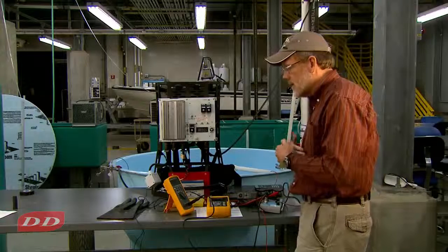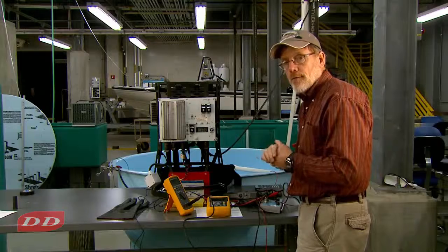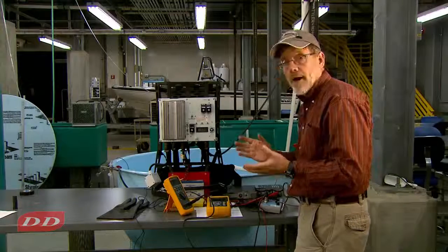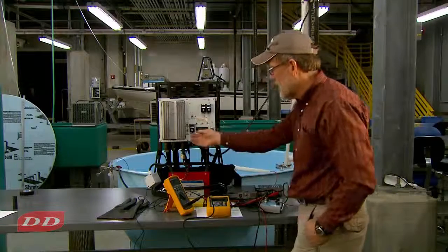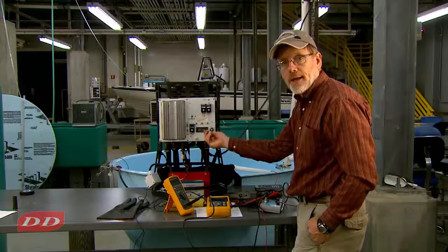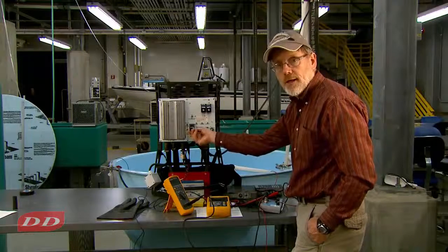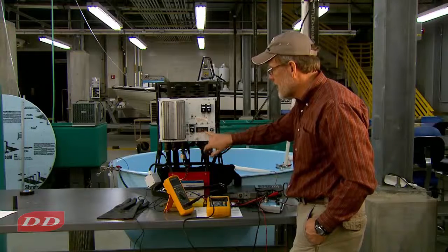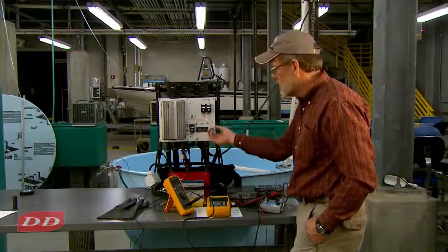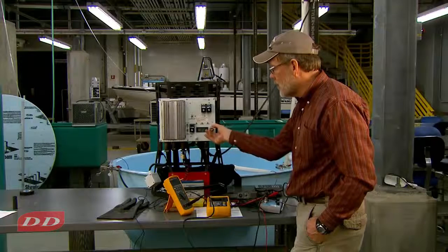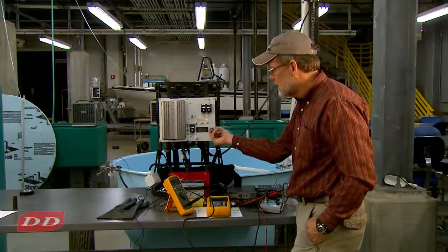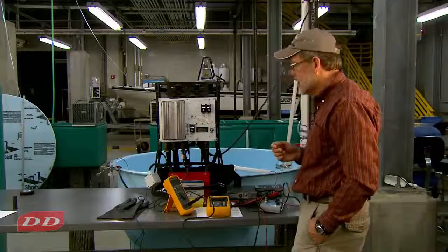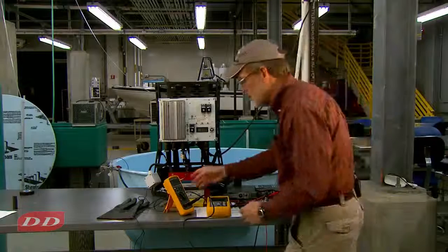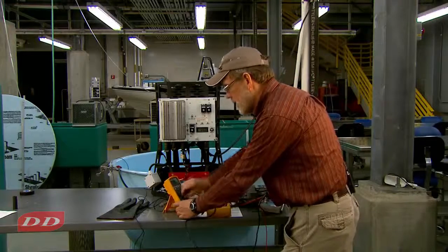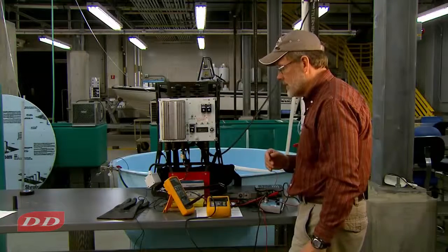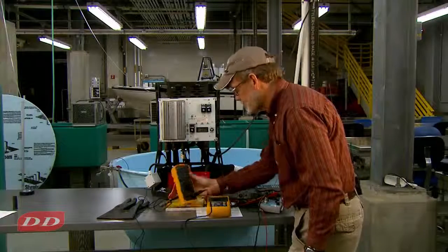Another important characteristic of waveform to look at is current, or amp draw. This particular unit, we don't have an amp setting dial. We only have a voltage setting dial. But we do in this particular unit have an ammeter. So it shares that function with the voltmeter. There it's a voltmeter. I turn the switch over to peak amps, and it's an ammeter. So we'll compare the reading we get from the multimeter with the meter reading on amperage.